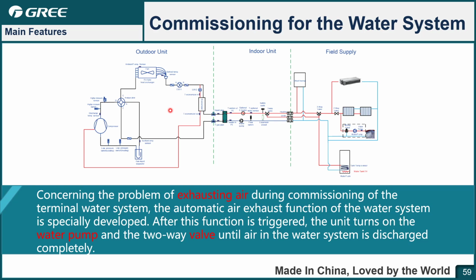The next one is the commissioning function for the water system. For new projects, there is a lot of air in the water system. So in order to exhaust the air inside, this unit can set the air removal commissioning. In this case, the water pump and all of the valves, 2-way valves, 3-way valves, will be opened to help you exhaust the air inside, and then the water pressure inside will be stable to avoid running problems.